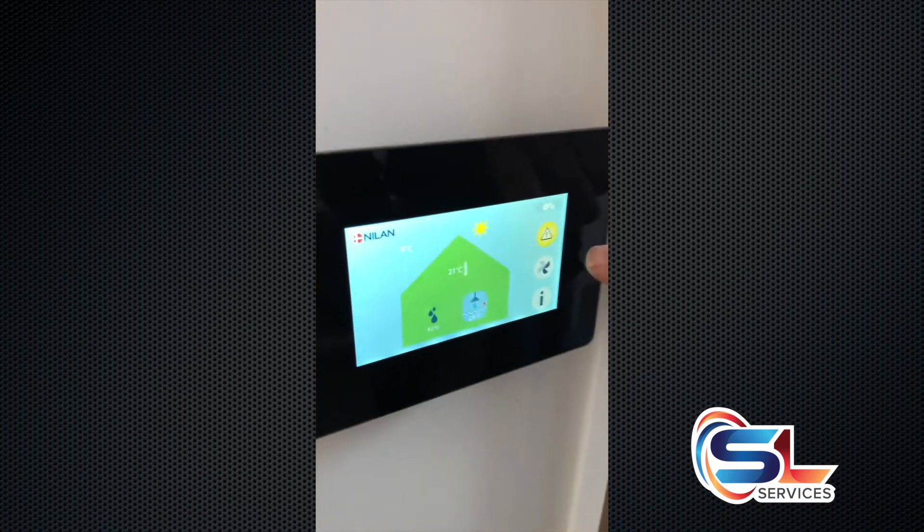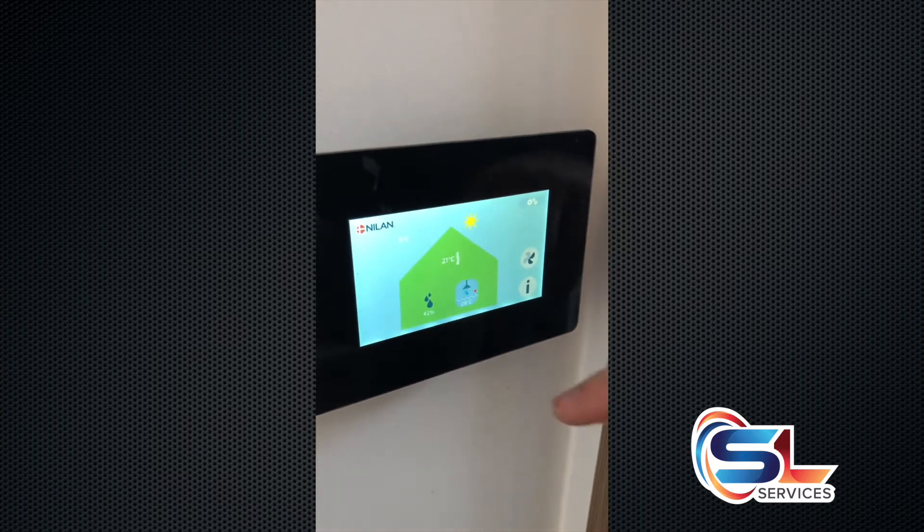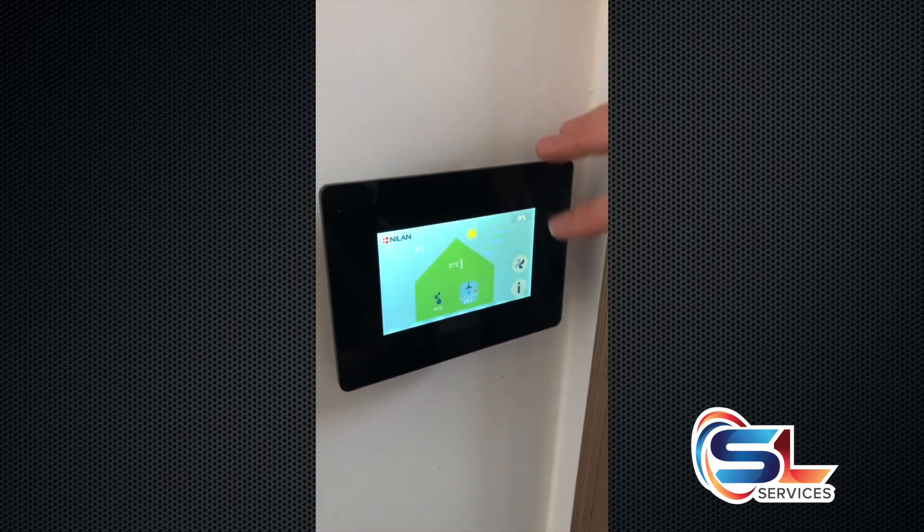The anode alarm is just here, so you can press that — it says 'anode fail', approve event. Your machine will continue to run anyway, so that's fine.